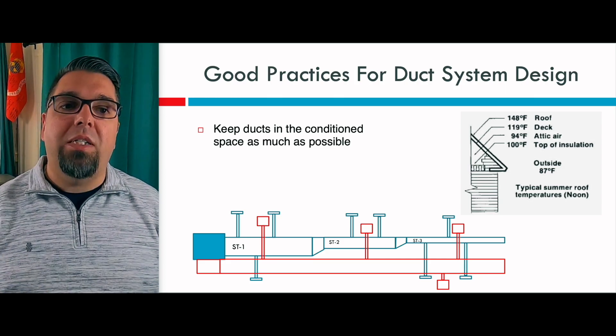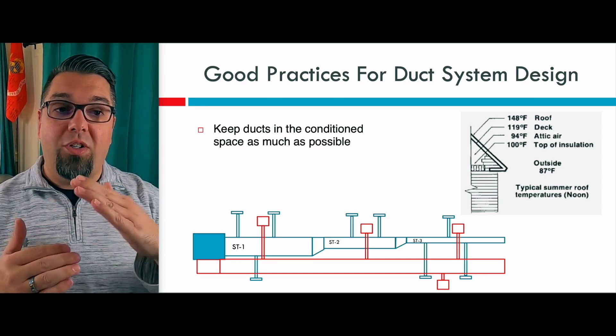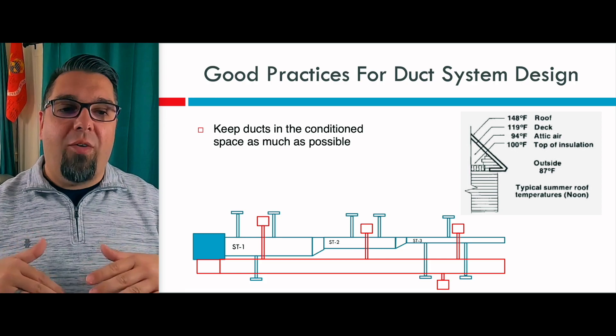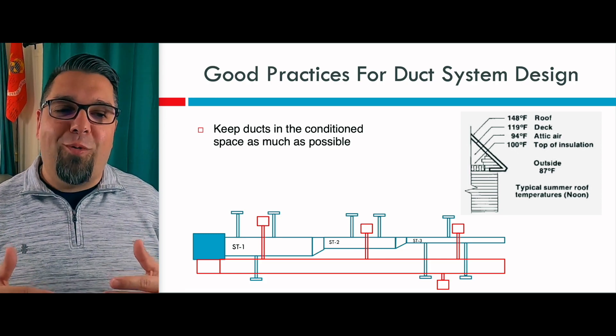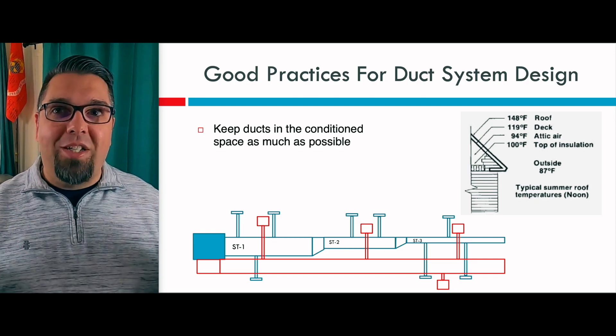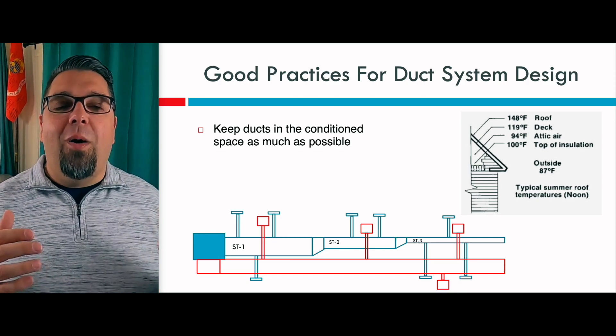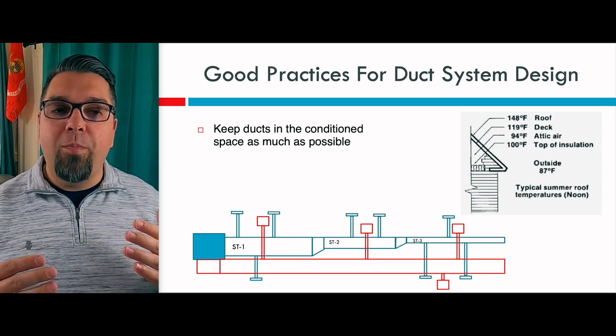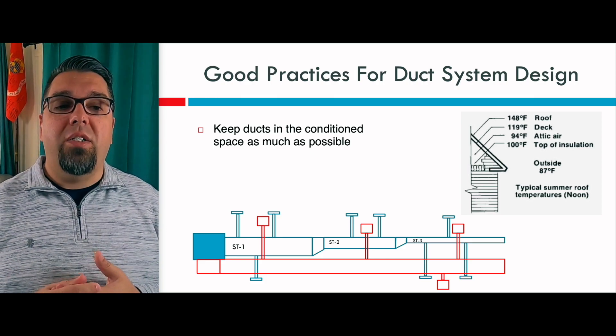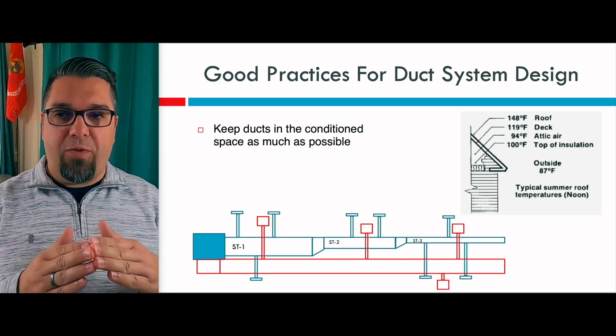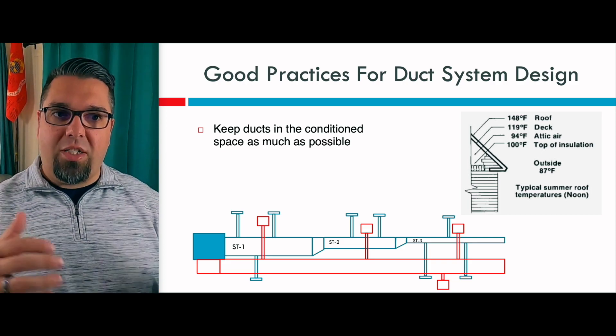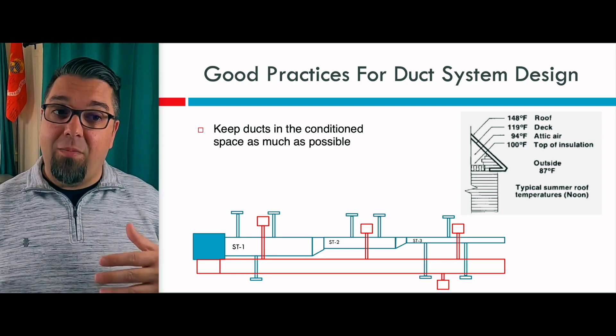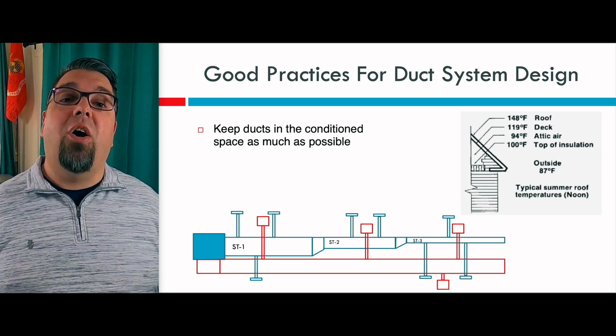The roof itself could be as much as 150 degrees — that's why we don't attach duct work to the roof, and we try to avoid using those cavities along the roof to keep duct off the floor of the attic. If you were to keep duct against an outside surface like a roof, a floor, or a wall, that's probably the worst place you can locate a duct. If it's everything within the building envelope, the temperature difference across that duct is nothing, because anything lost or gained is just going back into the conditioned space. This is why ductless systems tend to be smaller than ducted systems — because of where we're sticking all the duct work.